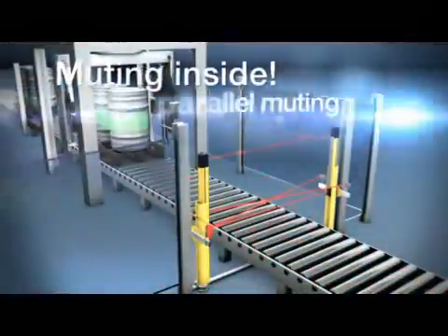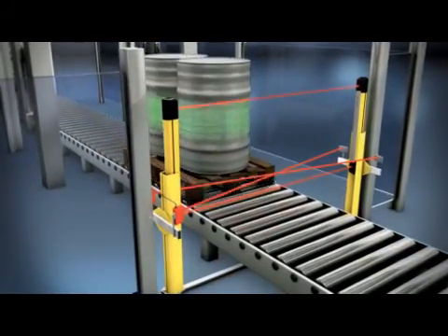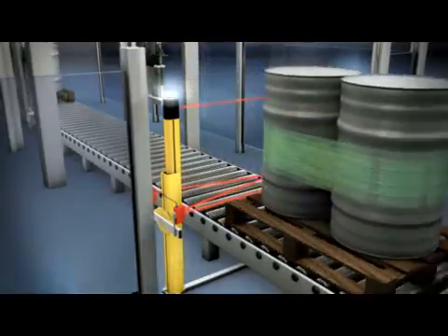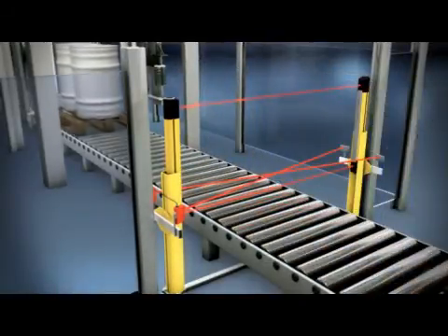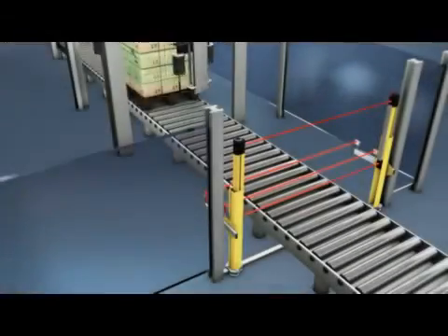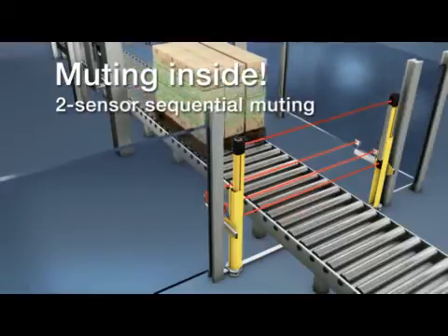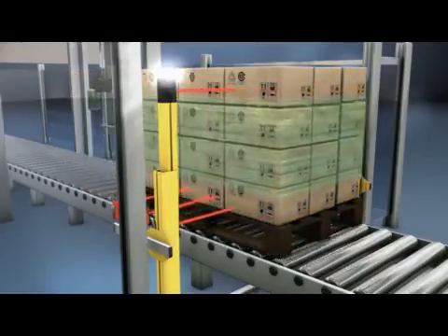The Leuze electronic MLD is capable of two-sensor parallel muting without additional devices and PC. Six different muting operating modes can be selected, simply by PIN assignment. Two-sensor sequential muting can also be configured, for shipments leaving the danger zone, especially when space is tight.